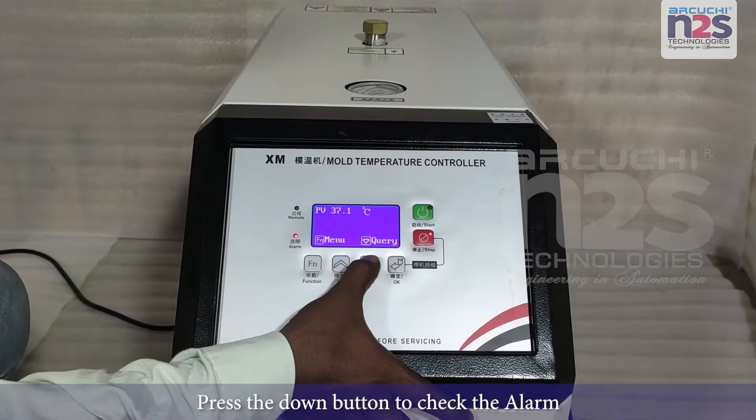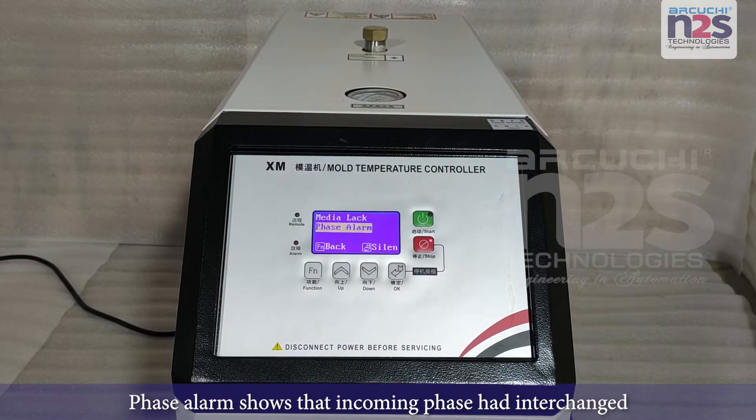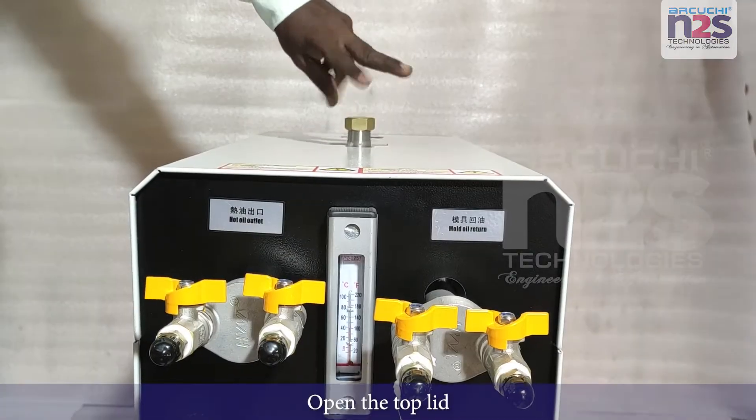Press the down button to check the alarm. Phase alarm shows that the incoming phase had interchanged. Media Lack Alarm shows the oil level in the tank is low. Open the top lid.